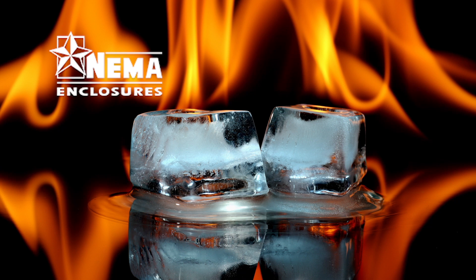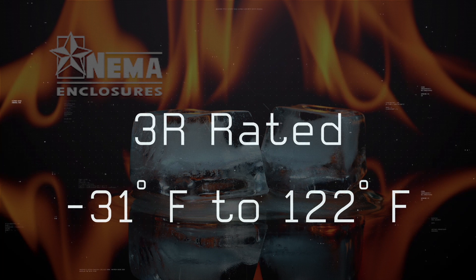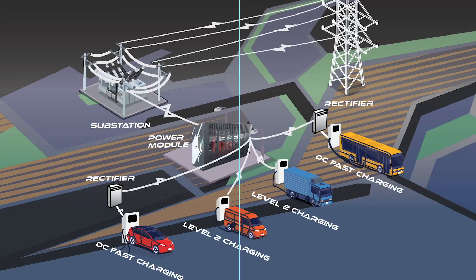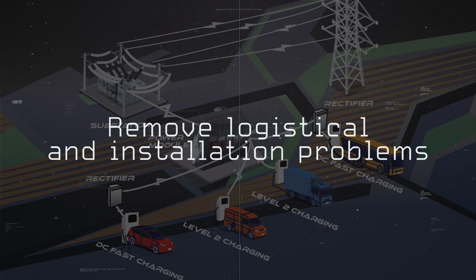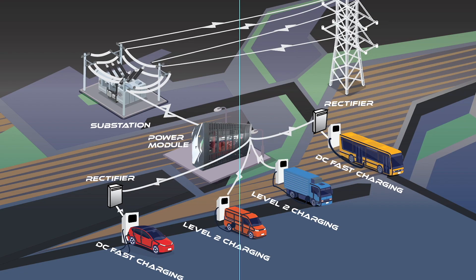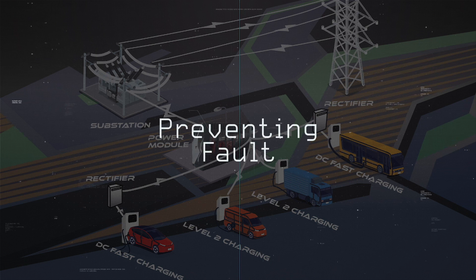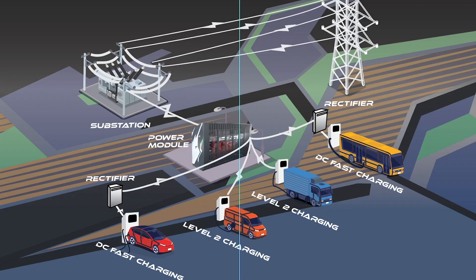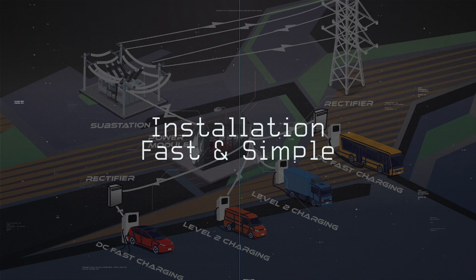All units have an AC output voltage of 480 volts AC three-phase at 60 hertz. E2V is NEMA 3R rated and can withstand operating environments ranging from negative 31 degrees Fahrenheit to 122 degrees Fahrenheit. E2V's innovative design removes logistical and installation complexities by providing a safe solution with medium voltage switchgear, preventing faults from traveling upstream, and a dry transformer that seamlessly steps down medium voltage to 480 volts, then to low power distribution and protection to chargers and rectifiers. No field integration is required.